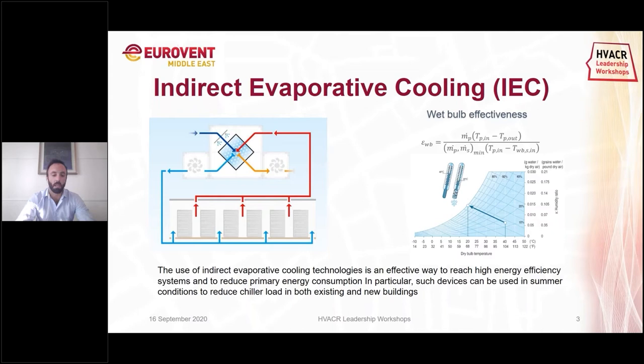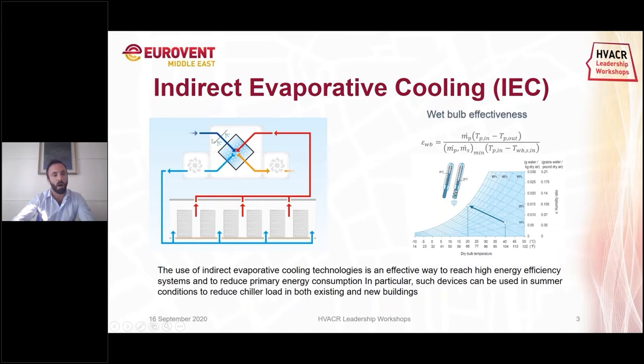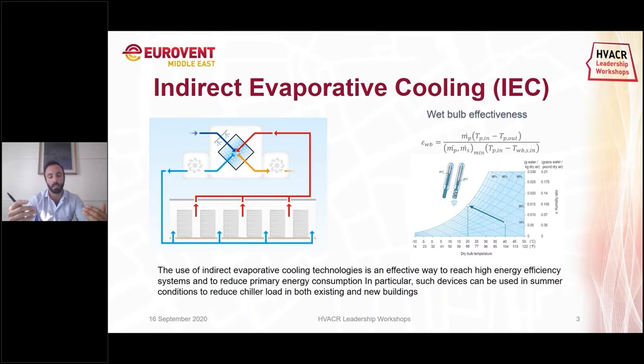The indirect evaporative cooling technology — the heat exchanger plus the adiabatic humidifier — is the most promising technology in this context. Because we are avoiding recirculation, we need to reduce running costs as much as possible, which are increasing due to full fresh air operation. This technology uses the adiabatic humidifier to wet the exhaust airflow, cooling down the other airflow. We work mainly on the wet bulb temperature of one airflow to decrease the overall temperature of the system.